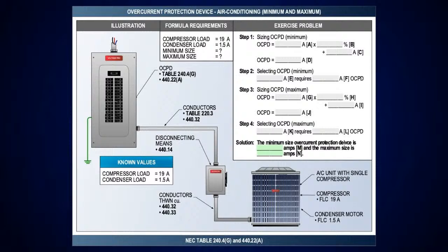So it's one unit, and therefore you're going to use the nameplate value that's on there. Okay. And in here, you've got a compressor of 19 amps and 1.5. You should automatically learn this. I'm going to go to 440.22A. I'm going to take it at 175%. If I need to do a maximum, it's 225%.